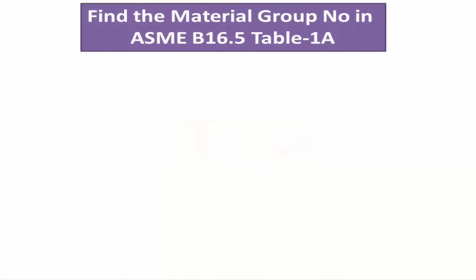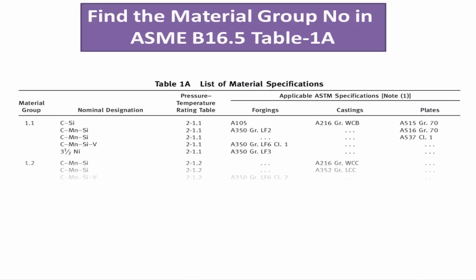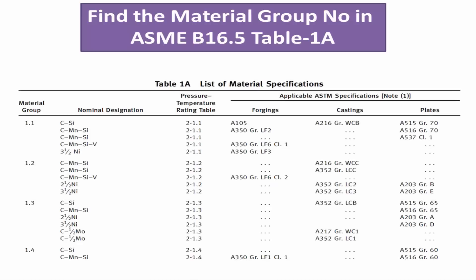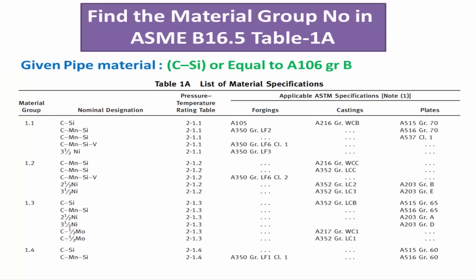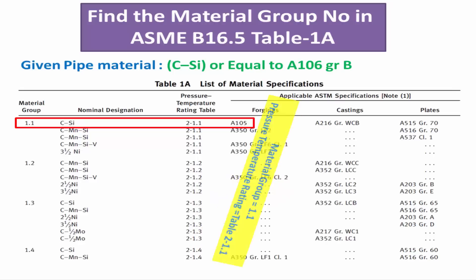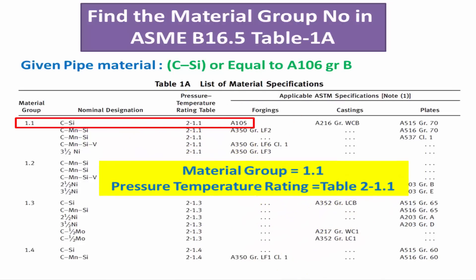Step 1: Find the material group number in ASME B16.5 Table 1A, and in parallel, select the pressure-temperature rating table. In our case, the material group number is 1.1, and the corresponding pressure-temperature rating table is Table 2-1.1.